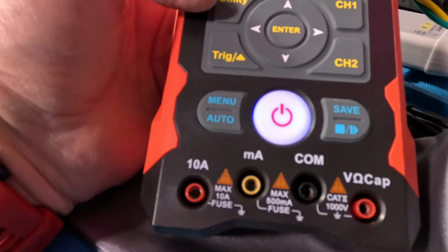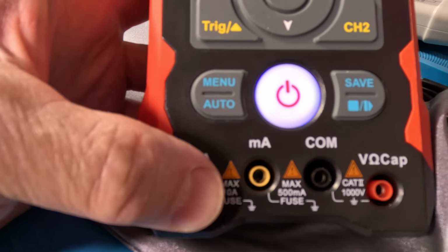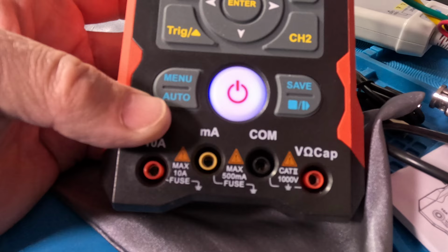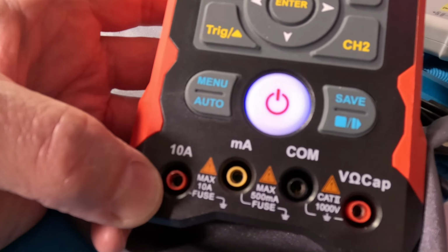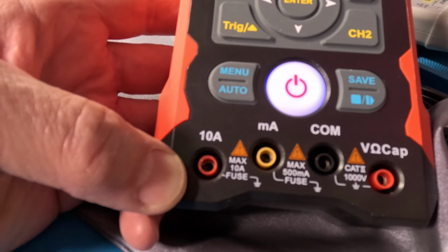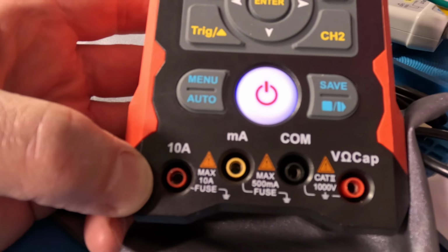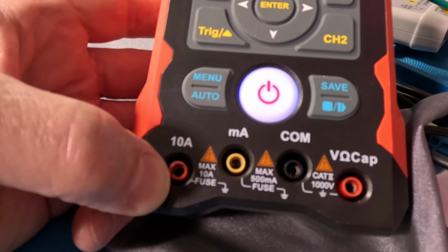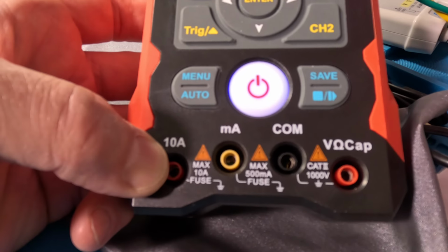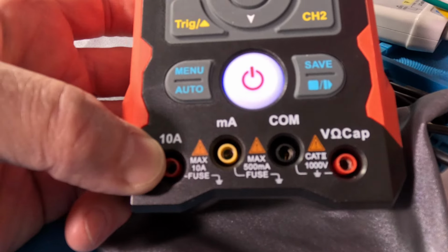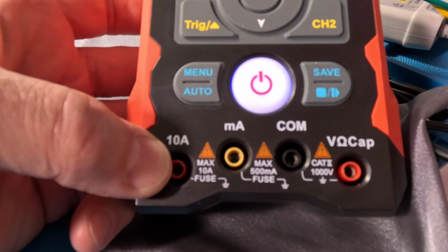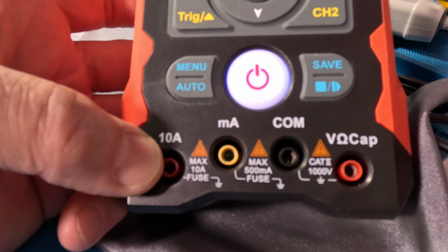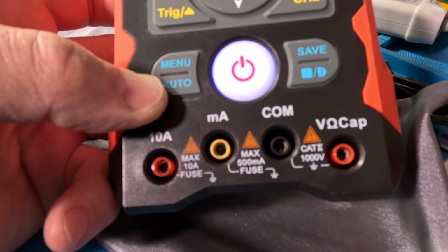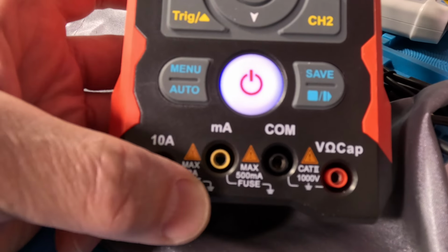Don't you guys? Now, down here at the bottom, we do have the milliamp, the amps, the common, and the volt ohms. And one thing I want to point out, see this? Category 2, 1,000 volts. So, guys, that means bench work, right? We're not going over to the breaker panel, which should be category 3. We're not going to the high voltage lighting that's between the main breaker panel and the outlets. That's all category 3. And outside, on the other side of the main breaker panel, is category 4. So this is category 2.